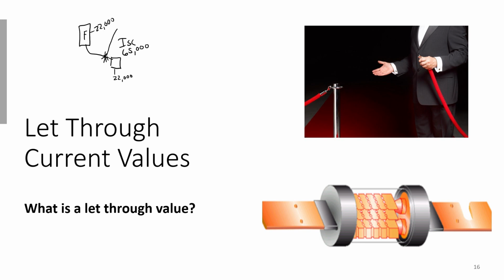They are not allowed to use the let-through current value in new installations. So you cannot do this. You can't design this. This has to be a last-ditch effort in an existing building to try to achieve safety. This is not our go-to. All right, so the degree of current limitation can be determined from the standards, from the let-through charts. The let-through charts are plotted from actual test data based on fault current levels, and they are available from the circuit breaker and fuse manufacturers. That's who gives them. The engineers read them.